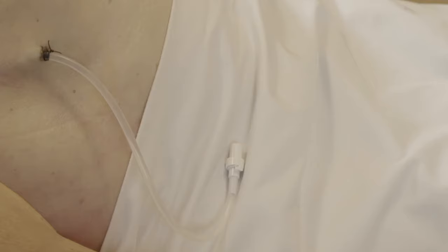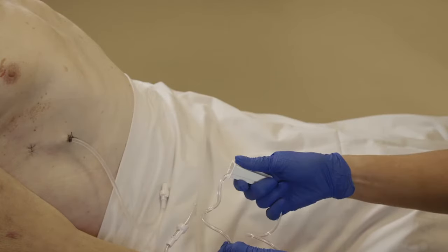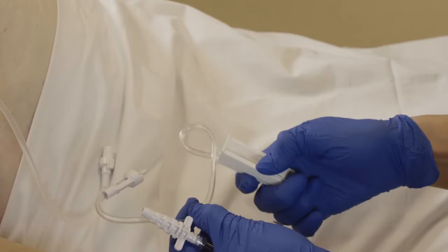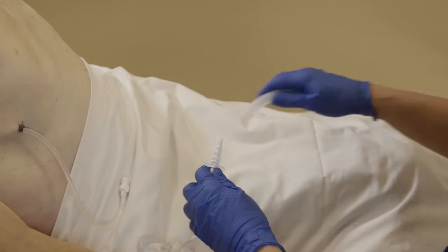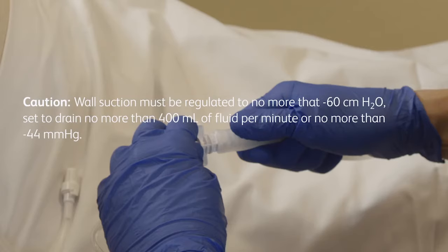To use wall suction and the PleurX lockable drainage line, first close the roller clamp on the drainage line by rolling the wheel toward the suction source. The roller clamp must be completely closed to occlude the drainage line. Attach the 5-in-1 adapter to the Luer fitting on the end of the drainage line, then attach the drainage line to the suction source. Wall suction must be regulated to no more than negative 60 centimeters of water, set to drain at no more than 400 milliliters of fluid per minute or no more than negative 44 millimeters of mercury.